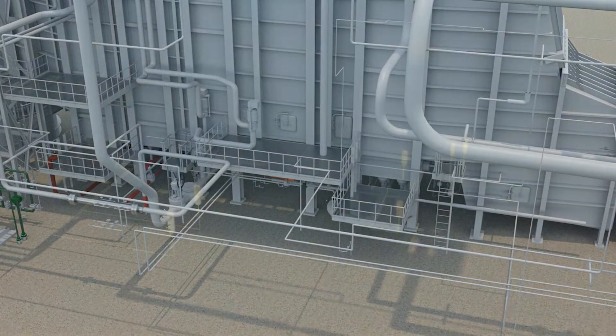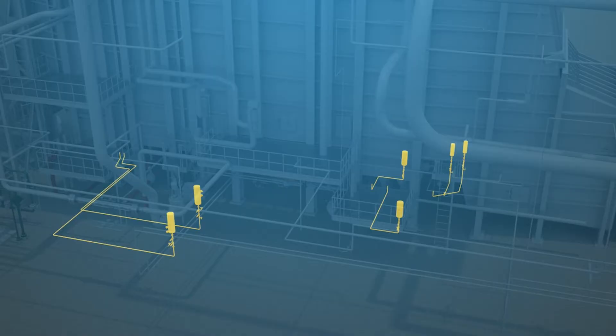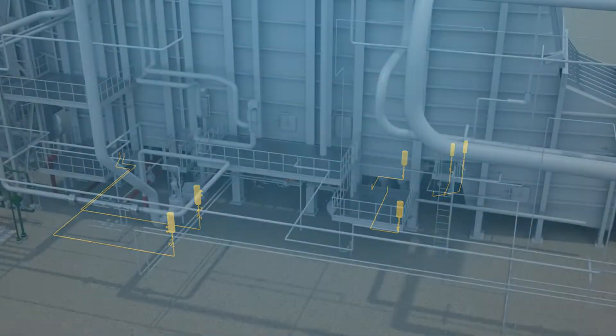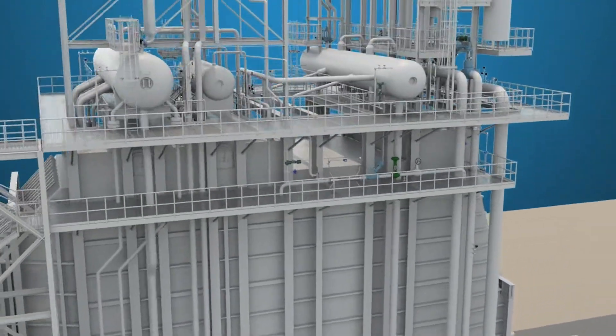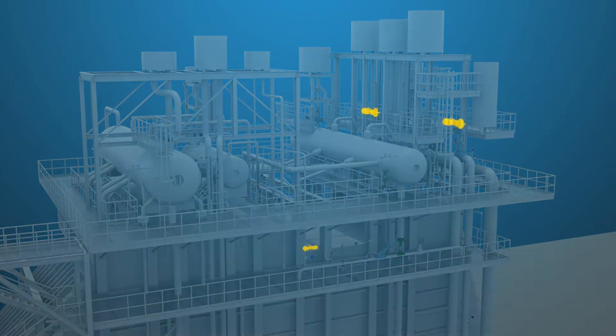Prior to starting the pump, all drain valves on the HRSG economizers and evaporators should be closed, and vent valves open to purge the air out of the system.